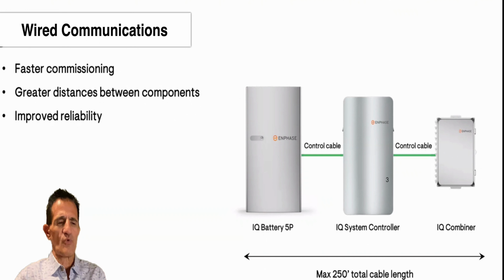The 5P also has wired commissioning. As I mentioned, a wired system is actually preferred because sometimes you might be at a job site where there's interference or not very good signal, and sometimes all the components can't go on one wall. Sometimes the battery is on an opposite wall, like a brick wall, and the communication signal doesn't go through it well. So it's better to have a wired system and not a wireless one. It improves reliability and means less problems, fewer service calls.